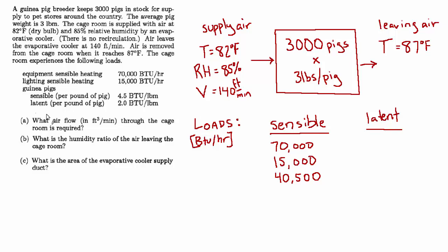And then there's also a latent component. These pigs are mammals, just like you and me, so there's perspiration and respiration, and that creates a latent load in the space. So that's 2 BTUs per pound, again, times 9,000 pounds. So that's 18,000 BTU per hour of latent load. So let's total that up. Sensible is going to be 125,500, and the latent is just the 18,000. That's the only latent load is from the pigs themselves.